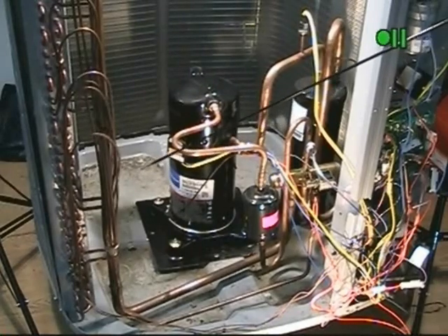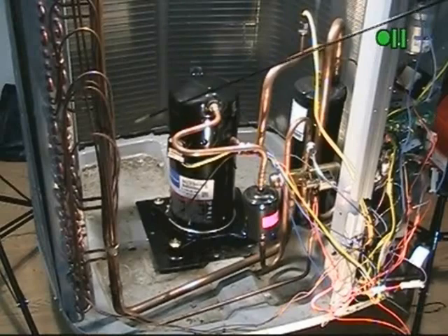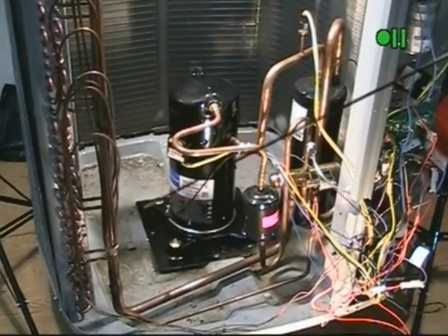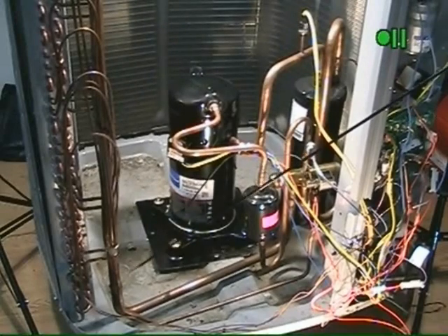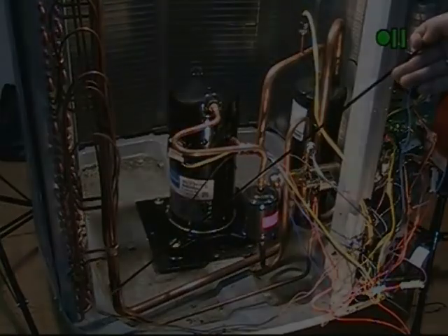As we learn to charge our systems in the AC mode, when we're feeding a TXV inside, we will use the process of subcooling to measure the amount of refrigerant in the system. When we measure subcooling on an AC system, we're basically just measuring this subcooling process. So our subcooling number tells us how much refrigerant we were able to condense. Most units will give a rating.